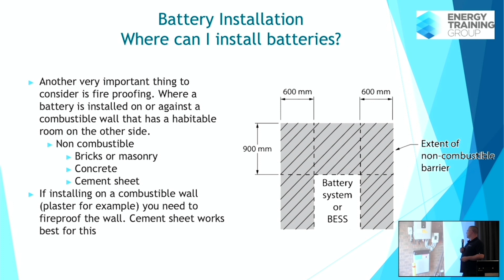This is an example of a wall that we'd fireproof before installing a battery. Two sheets, because we've got 600 mil of cement sheet here to here, and we've got to stay 600 mil away from the door. The inverter can go within the exclusion zone - only the inverter or the switchboard. Any other appliances cannot be within that exclusion zone.